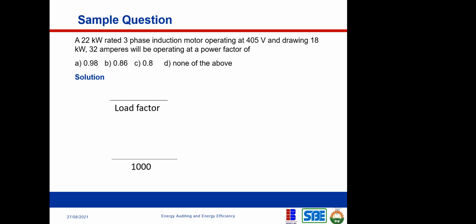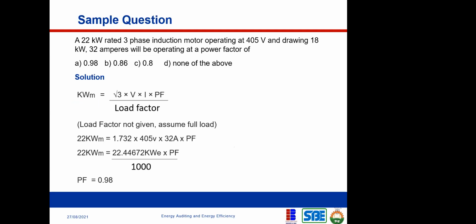So it's important that we understand the difference between kilowatt electrical and kilowatt mechanical. I've told you that the ratings on electric motors are the shaft power output, which is kilowatt mechanical. So here is the solution. The kilowatt mechanical is equal to the kilowatt electrical times, in this case, we are not given the load factor, are we? If you're not given the load factor, we assume it to be at full load, which is 1. I stated here, load factor is not given, so assume full load, which is 1.